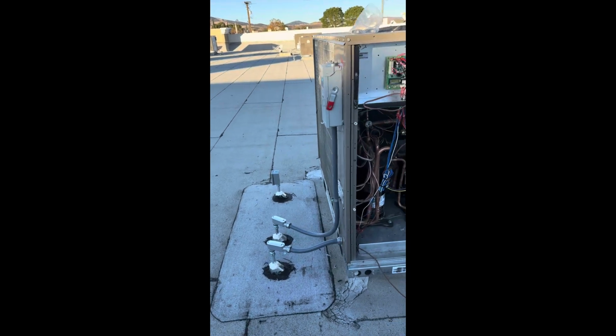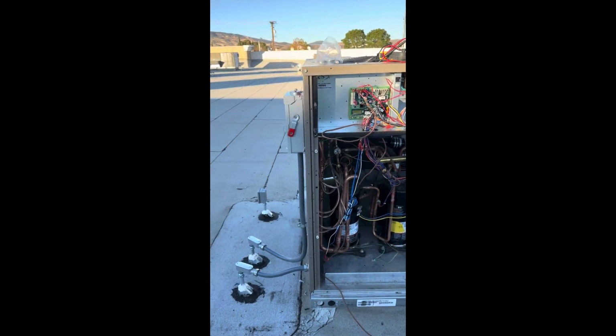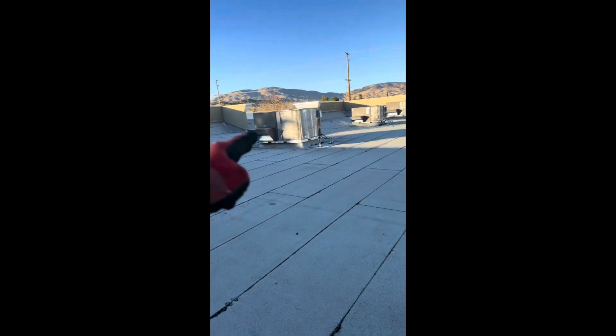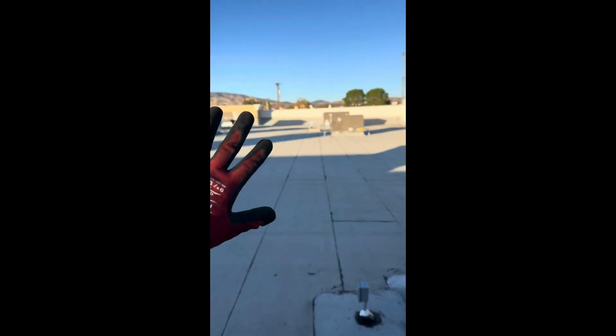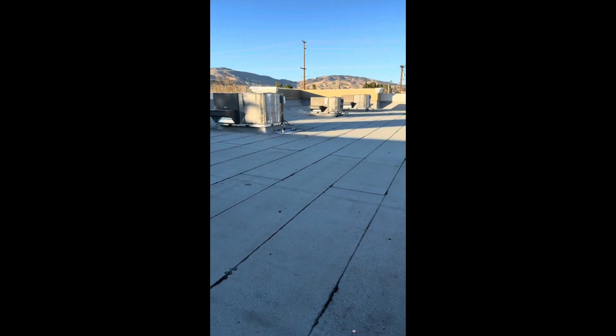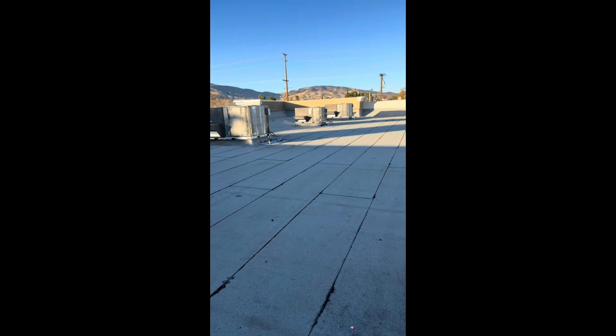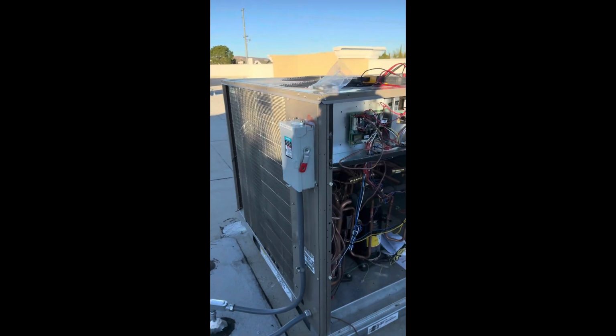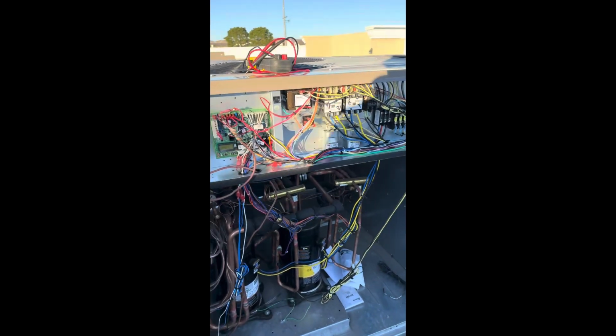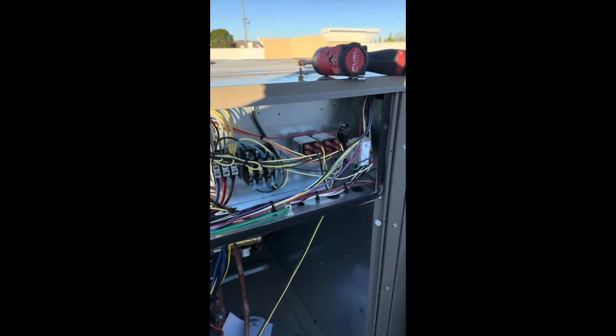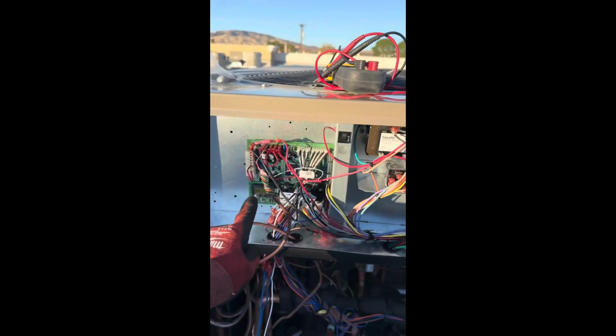Okay everyone, so to start off again, we're back at this York startup. We already have all these RTUs started up, no problem. Economizers are wired in. Every thermostat is properly wired for heat pump mode. However, on this last heat pump, we found a low voltage short that was tripping this particular transformer. Now this one powers my low voltage unit control board here.